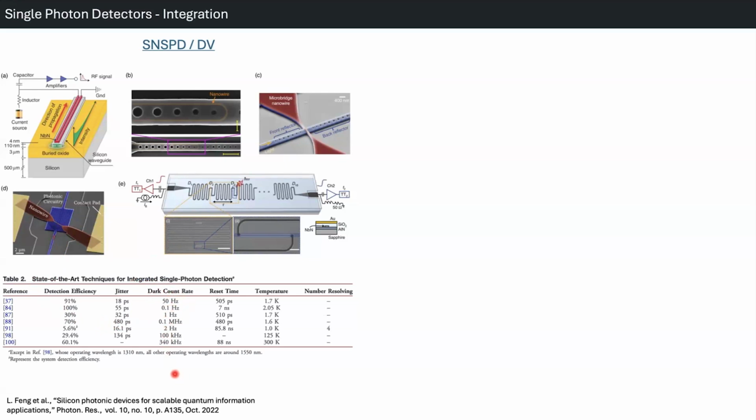Here we see that operating temperatures depend on your structure. For example, this 300K is silicon, but the others are superconductor structures. It's very reasonable: 2K. For the 2K structures, you just need an ordinary continuous flow cryostat. You can just use ordinary purified helium for the system.